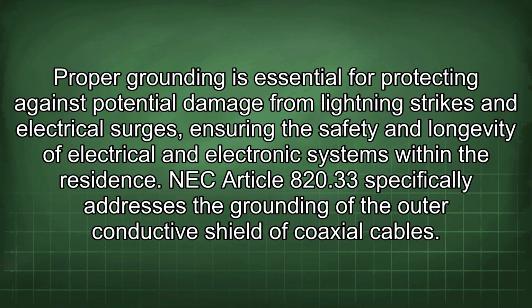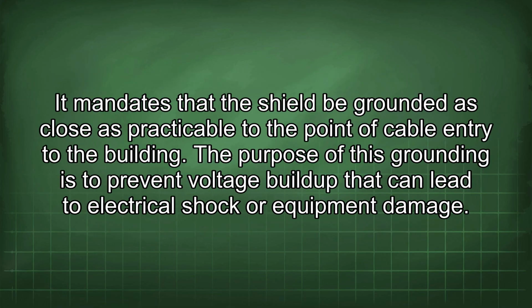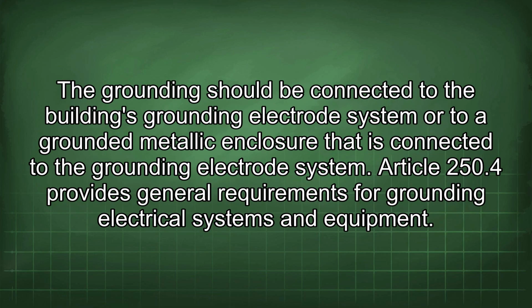NEC Article 820.33 specifically addresses the grounding of the outer conductive shield of coaxial cables. It mandates that the shield be grounded as close as practicable to the point of cable entry to the building. The purpose of this grounding is to prevent voltage buildup that can lead to electrical shock or equipment damage. The grounding should be connected to the building's grounding electrode system or to a grounded metallic enclosure that is connected to the grounding electrode system.